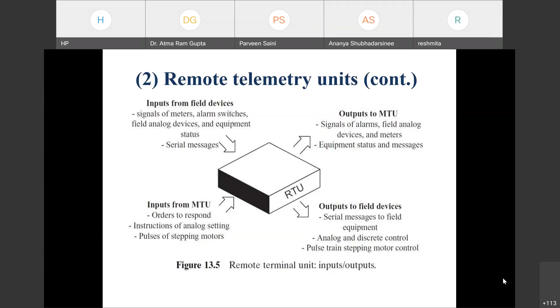Now, the output to MTU are the signals of alarm, field analog devices and meters, and equipment status along with the messages of the command. And now the outputs from the RTU are the outputs which go to the field devices. So they are the serial messages to the field equipment, analog and discrete control, and they are in the form of pulse train stepping motor control. So this is how this remote telemetry unit works on the commands and the input from the field devices, and it fetches back the commands to the field devices.